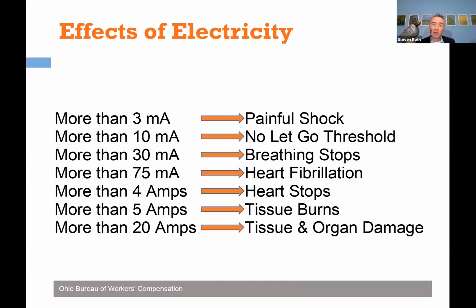The severity of a shock relates to the amount of current and how long you're in contact with it. If I hold on, my duration keeps increasing, so more current flows through my body. At 30 milliamps we can stop breathing. At 75 milliamps we start seeing serious complications like heart fibrillation. Even at 4 or 5 amps, we're looking at tissue burns, heart stopping, fibrillation, breathing stopping - none of that sounds good.